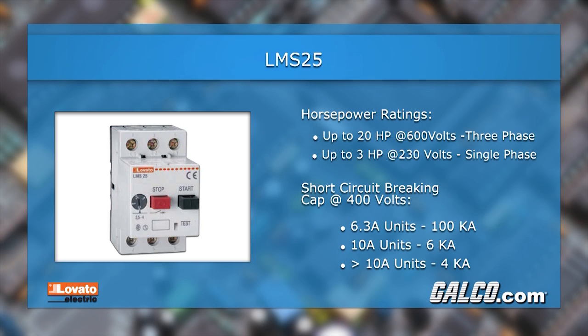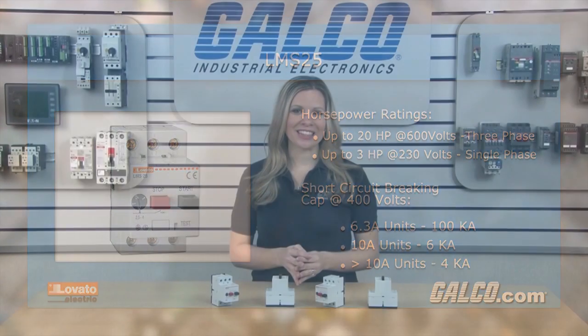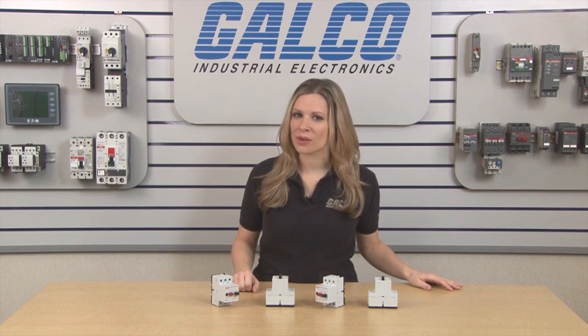For units rated at 10 amps, the short circuit breaking capacity is 6 kA, and for units above 10 amps, the short circuit breaking capacity is 4 kA. They are UL listed as a Manual Motor Controller and are compliant with IEC 60947 standards.